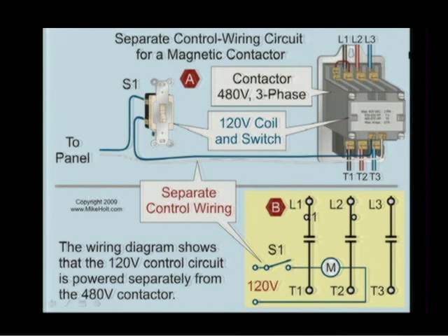It's really not related to the point here, but let me ask you guys. What is the practice in the industry for you, Steve? What have you seen? In our area it's brown, orange, yellow for the higher voltage, black, red, blue for the lower. You might get into some industrial locations where they might use all black and number them or something, but general commercial wiring, it's going to be brown, orange, yellow. Eric? Well, for us, 480 is low voltage, so it's black, red, blue. Is that really true? Yes, it is. I know low voltage is low voltage. 480 is low voltage at Dow Chemical, and so, yeah, it's black, red, blue. Okay. Dennis? Our industry standard is the same. We normally use brown, orange, yellow.